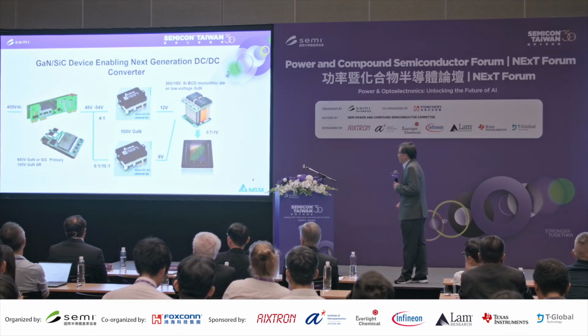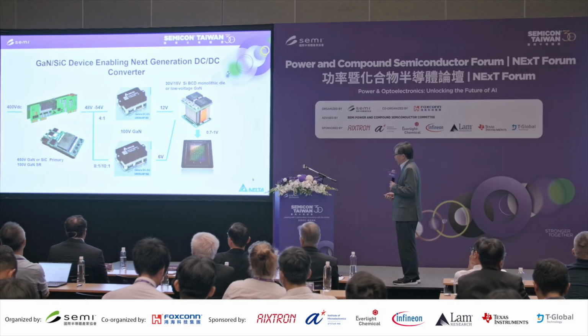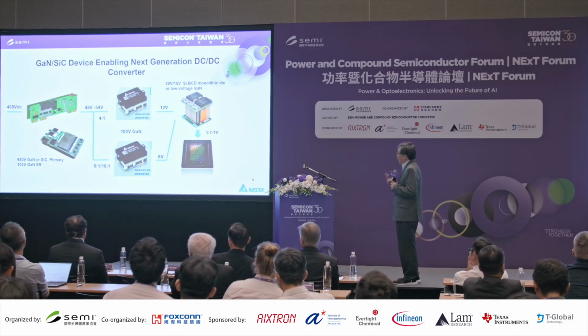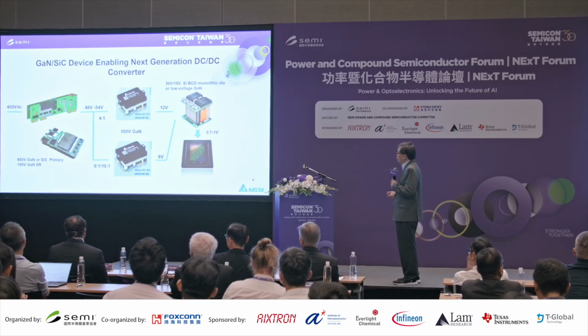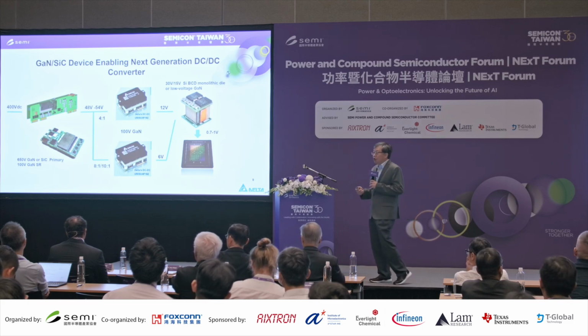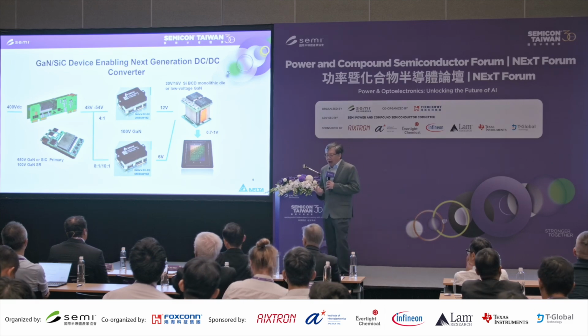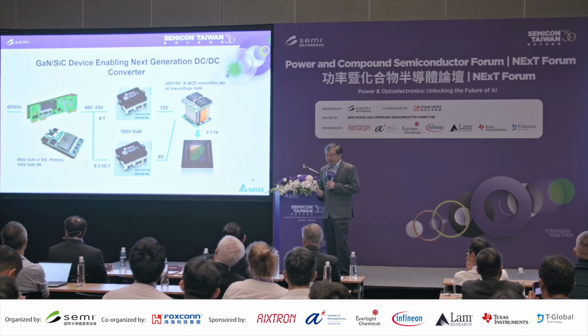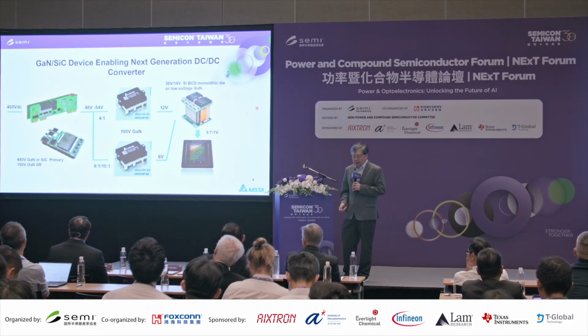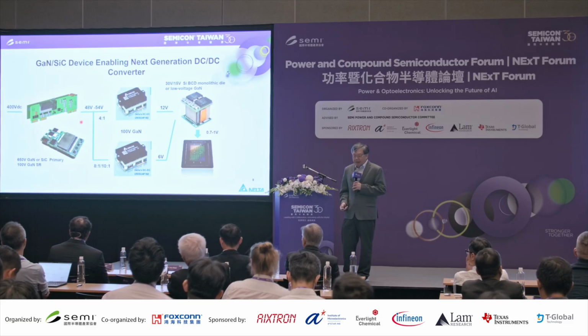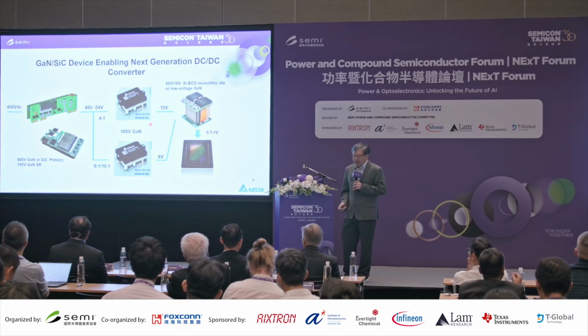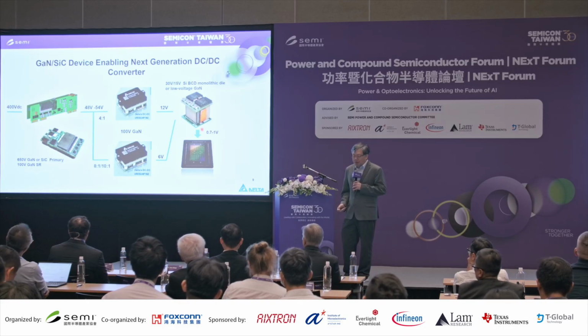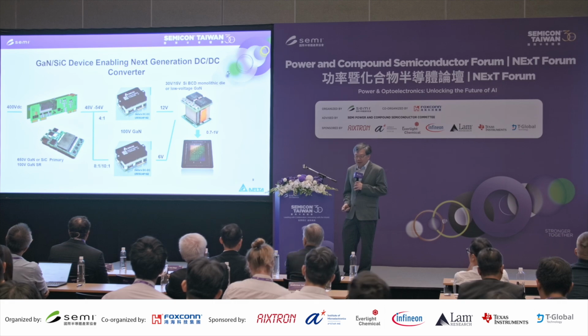So it's more Delta and also Cyntec. We have realized this DC-DC converter all the way from 400 volts to 0.75 volts. So it becomes all modularized. The reason we made them all modularized is because modularization can provide higher power density within a very limited space. At the first stage, we have 400 volts down to 48 volts, then the IBC conversion, either 4 to 1 or 8 to 1, and the final stage will be 12 to 0.75 or 6 volts, depending on your design.